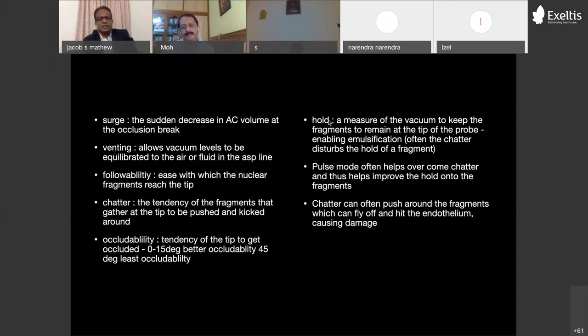Occludability, as I mentioned, is better with the flatter tips, whereas with a sharper tip you have to bury your tip a lot more before you start getting your hold, because the occlusion happens a lot later compared to a 0 or 15-degree tip. So if it's a hard cataract, you have to go for a 45-degree tip, whereas if you're doing a direct chop, you can go for your flatter tip. So a balance would be something like a 30-degree tip, which will be ideal initially. If it's a harder cataract, you can go for a 45-degree tip.